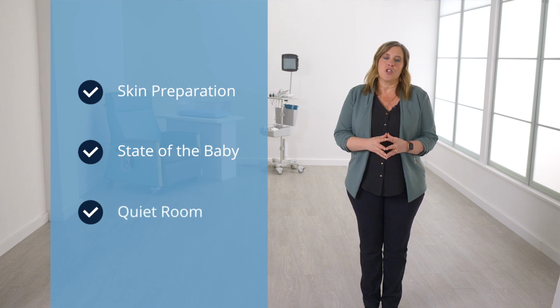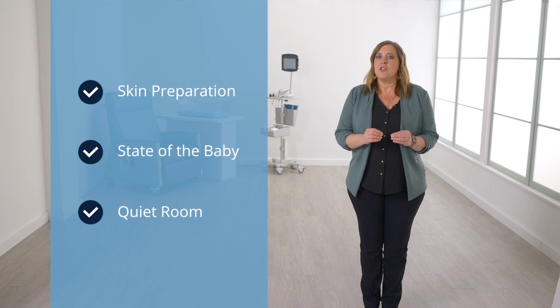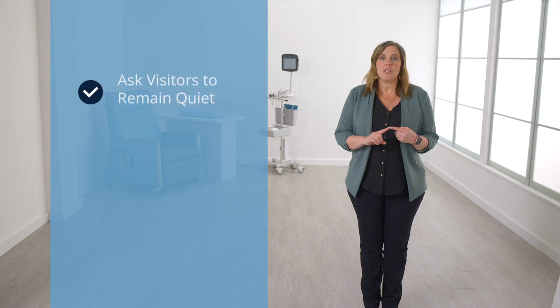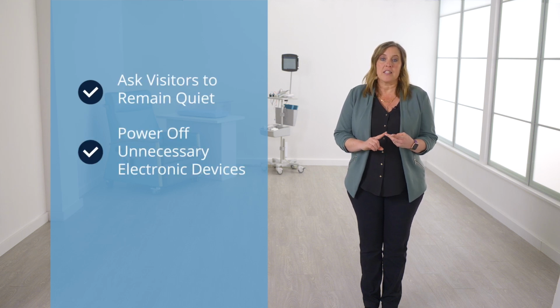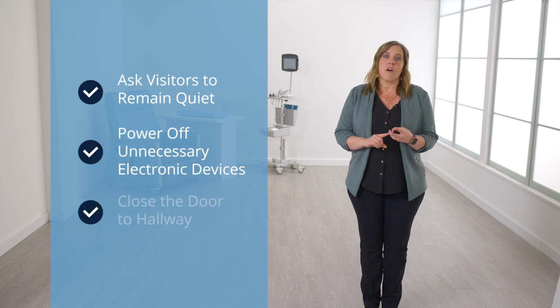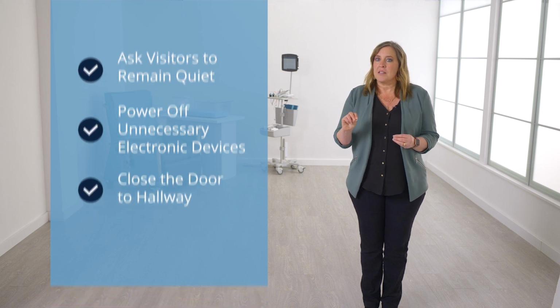Noise can sabotage a newborn hearing screening test. The noise bar on the Novus does not differentiate between acoustic and electric noise. Therefore, use these tips to eliminate noise and improve test conditions. Ask parents or visitors to remain quiet. Ensure that all unnecessary electronic devices are powered off and close the door to the hallway. If noise persists, try to move the bassinet to a different location within the room. Oftentimes, moving the baby toward the door gets them away from sources of electrical interference.